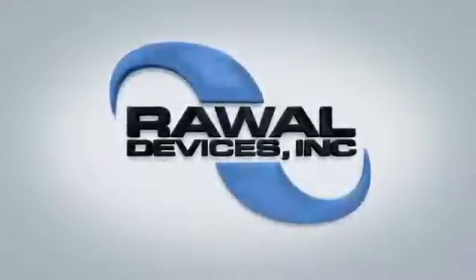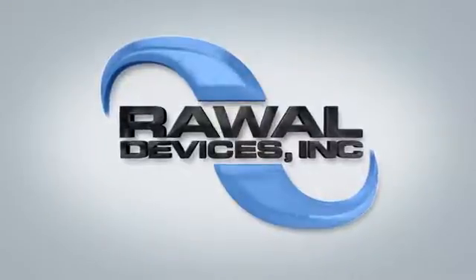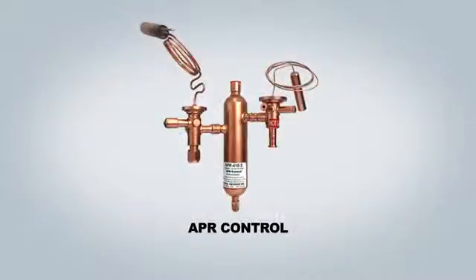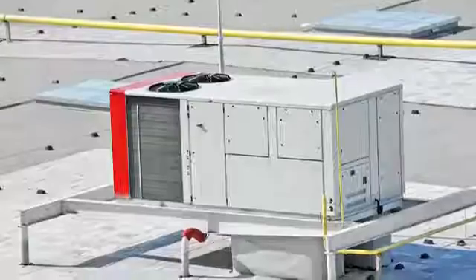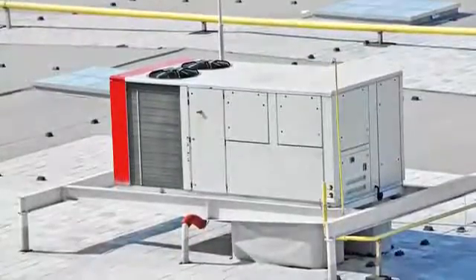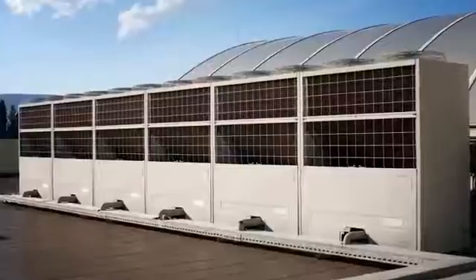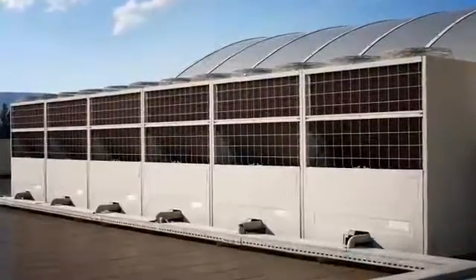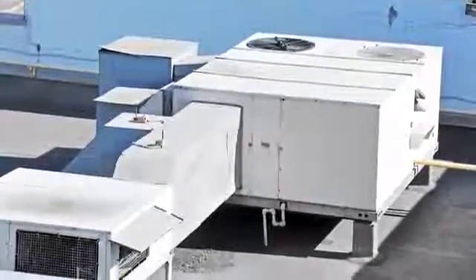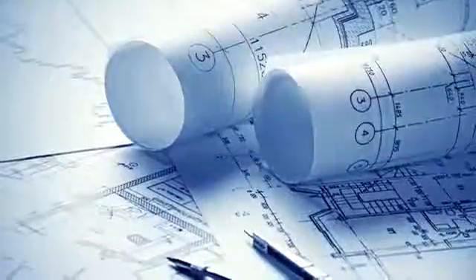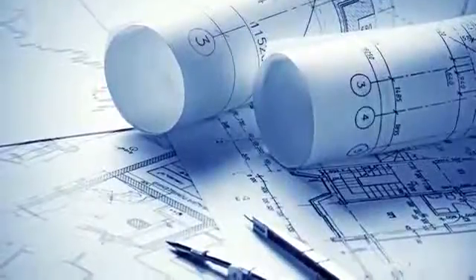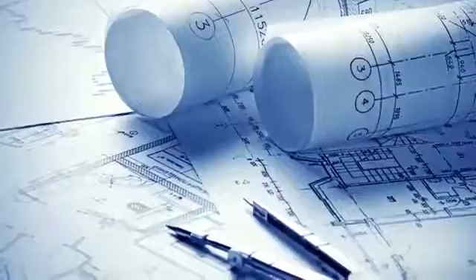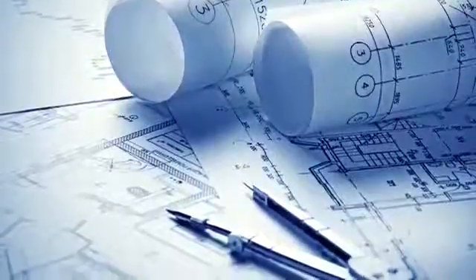Rawal Devices is the exclusive manufacturer of the APR control. The APR control is a capacity modulation and dehumidification device that solves oversized DX air conditioning challenges in commercial and industrial applications. Air conditioning equipment is designed for peak load conditions, which only occur approximately 5% of the year, meaning 95% of the year, equipment is oversized.